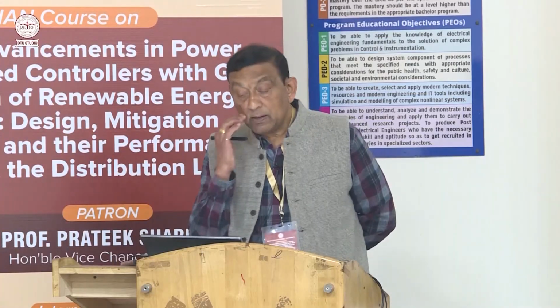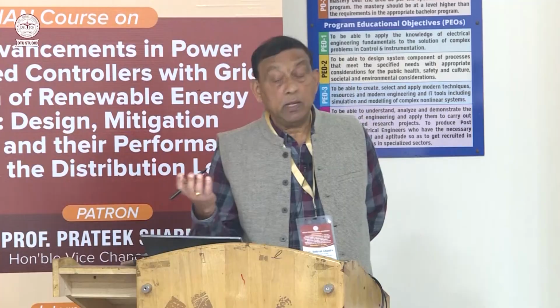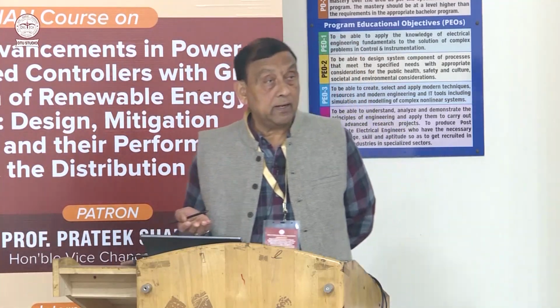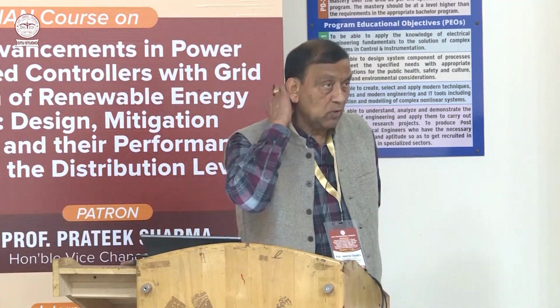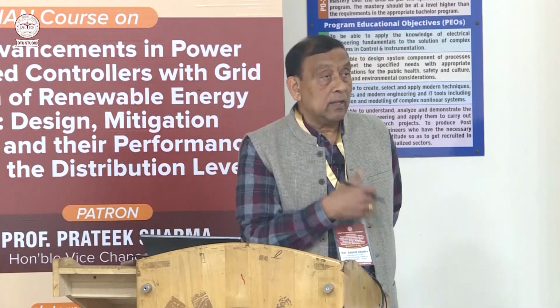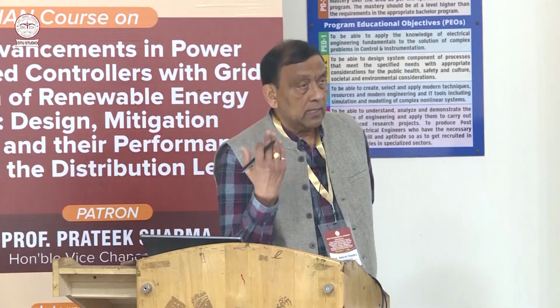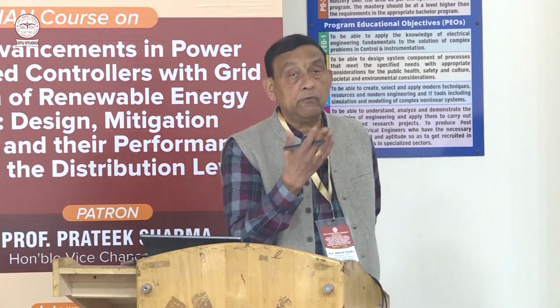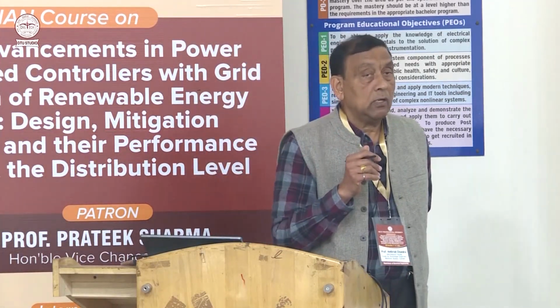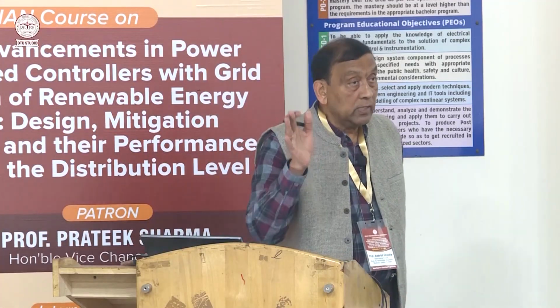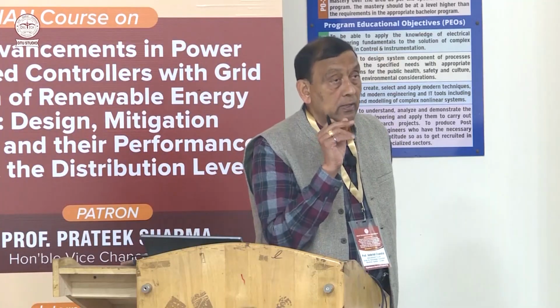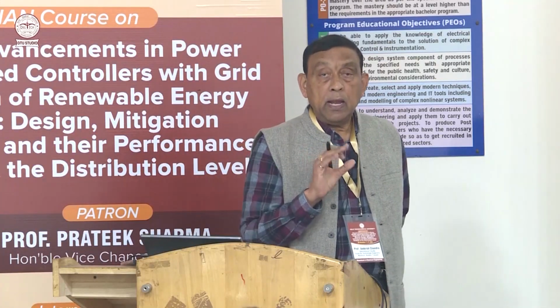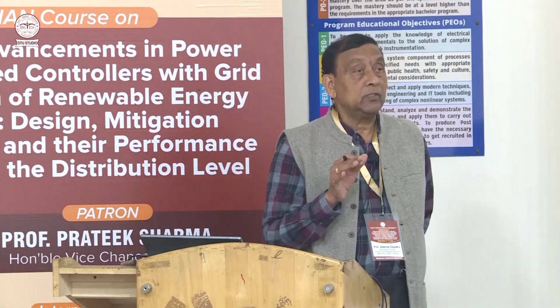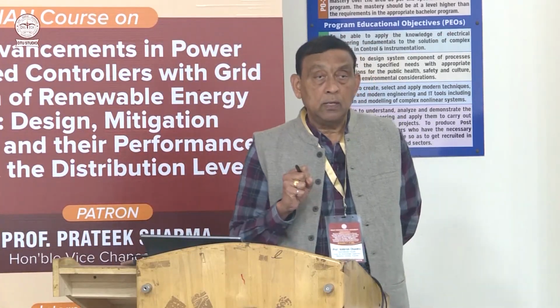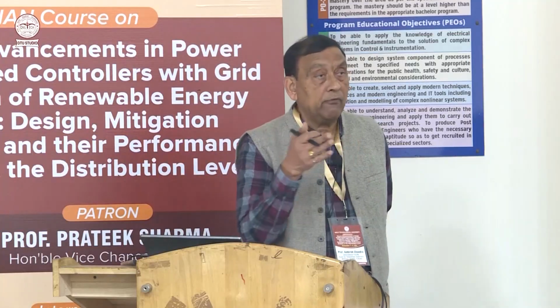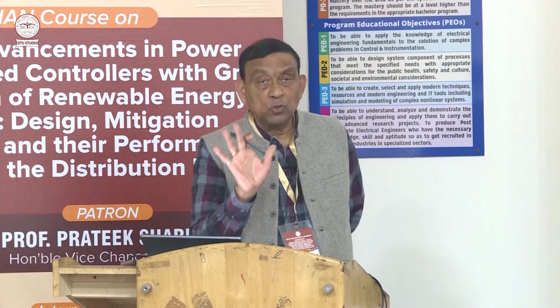And you already know that the frequency is basically the dynamic equilibrium between the load and the power generated. So as you already know, in big power plants, suppose there is a hydropower plant and there is a speed governor and water is flowing, the speed governor is keeping the speed constant. So that's why you have the constant frequency, 50 Hertz or 60 Hertz. But if there is a sudden, big change on the load, and if the load is increased too much, then it will generate currents flowing in the stator winding, and a large electromagnetic torque is generated, which will have a braking effect on the rotation of the rotor. In the meantime the governor takes effect, flowing more water, so that the speed remains constant.